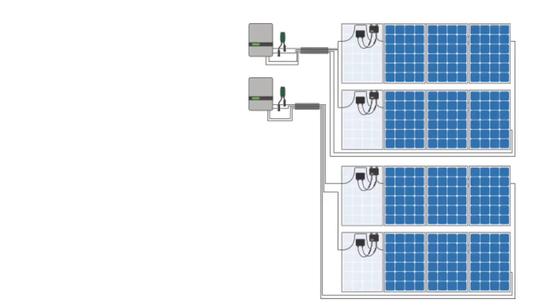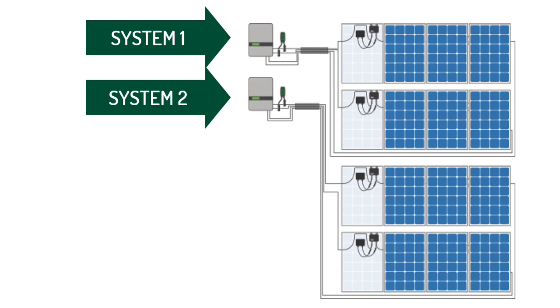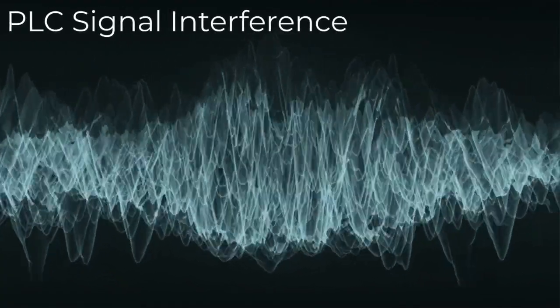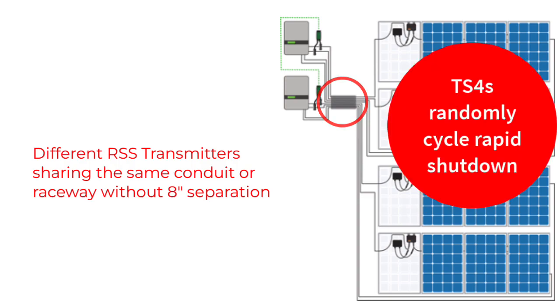When using the RSS transmitter, the DC home runs must be separated by at least eight inches from different RSS transmitter systems. If you're using multiple inverters on site that have either an internal Tigo RSS transmitter or the external RSS transmitter kit, the DC wires that flow through the cores create a system, and that RSS transmitter system must be separated from other PLC RSS transmitter systems. If not, the two systems will intermingle their keep-alive signals, which will cause confusion on both strings belonging to the two different systems, resulting in abnormal behavior for the TS-4s.